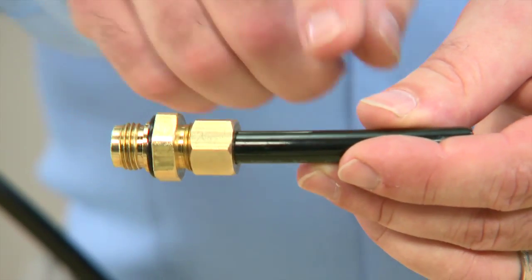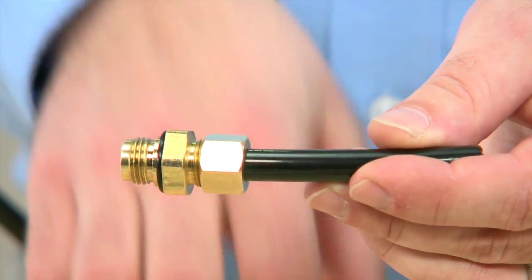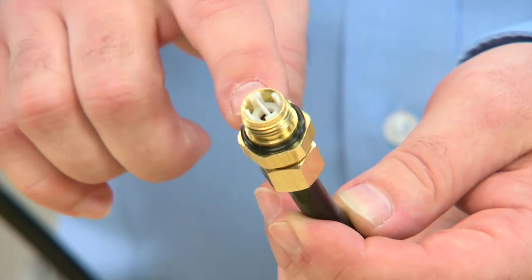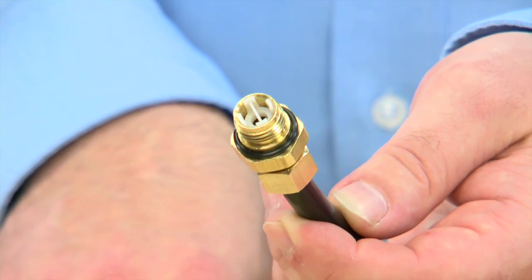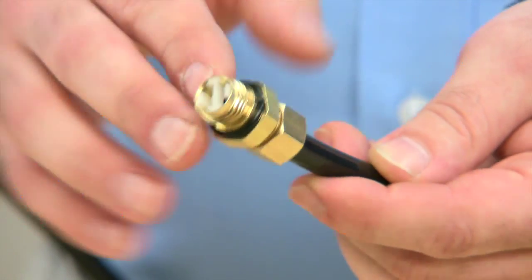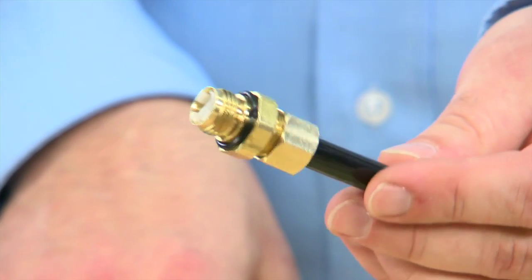There are four components: our hose, the nut, the connector that is inside the nut, and the end o-ring. This o-ring seals between the brine line flow control and the body. If there is damage to this o-ring, it will not seal properly. Any damage requires replacement of the o-ring.